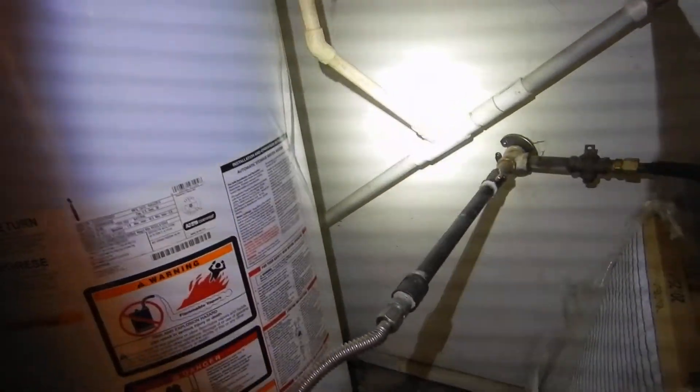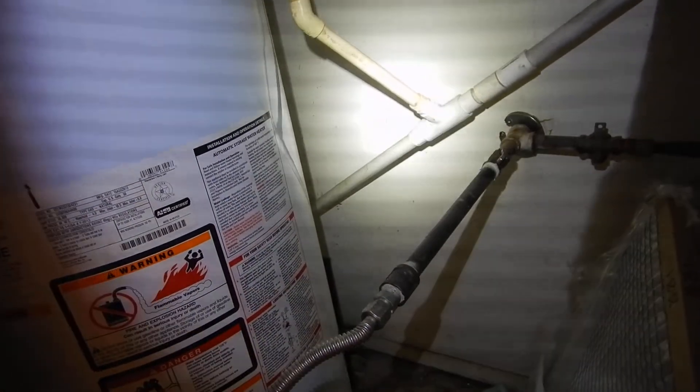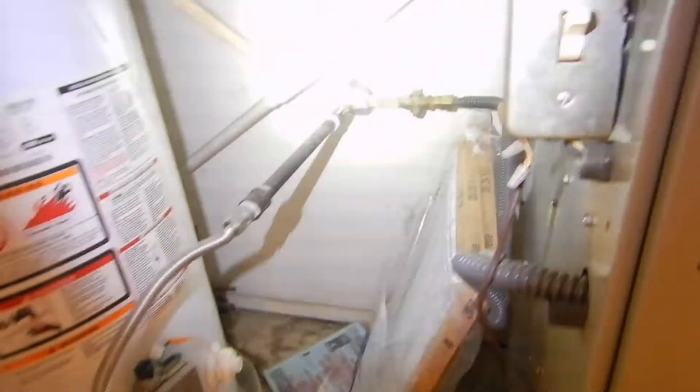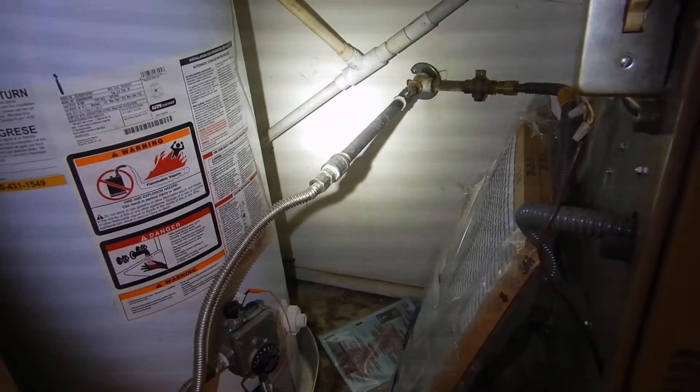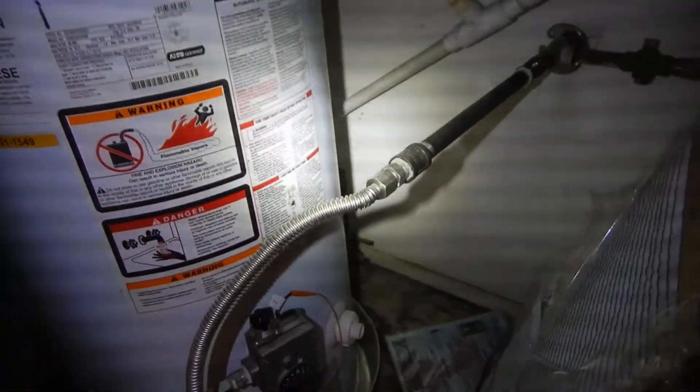Temperature pressure relief valve drain line does not discharge into an obvious location. Temperature pressure relief valve drain line is commingled with an HVAC evaporator coil drain line.